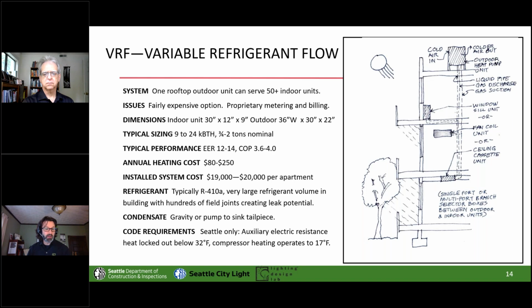It's the same truth on VRF. There's a limited lift, though it is larger. We recently did a high-rise building that lifted 8 stories, and those were like 11 feet floor to floor. They had slightly higher ceilings. So it was a close to 100-foot lift, but it definitely had an efficiency impact, and it also had some early compressor failures that have us a little worried. So that might have been a manufacturer thought they could, and we might not actually be true by the time we're done. All right, thank you for the note.